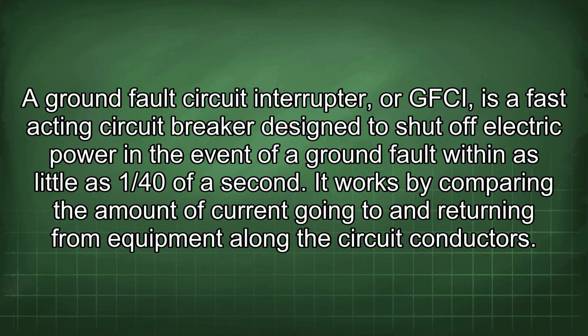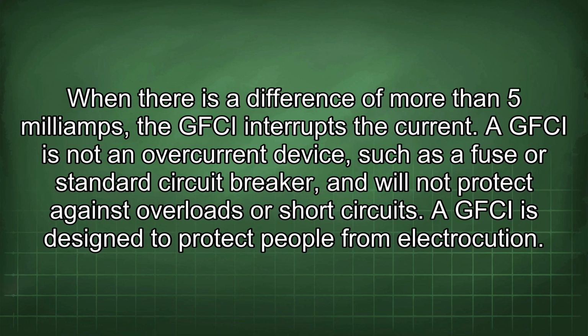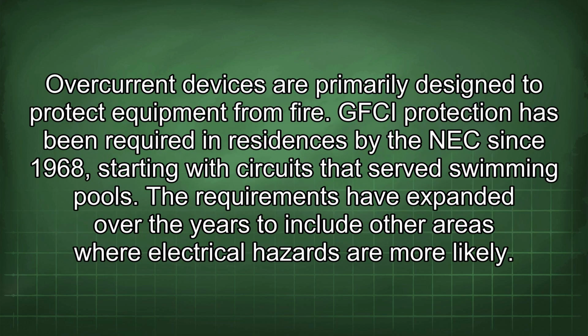A ground fault circuit interrupter, or GFCI, is a fast-acting circuit breaker designed to shut off electric power in the event of a ground fault within as little as 1/40 of a second. It works by comparing the amount of current going to and returning from equipment along the circuit conductors. When there is a difference of more than 5 milliamps, the GFCI interrupts the current. A GFCI is not an overcurrent device, such as a fuse or standard circuit breaker, and will not protect against overloads or short circuits. A GFCI is designed to protect people from electrocution. Overcurrent devices are primarily designed to protect equipment from fire.